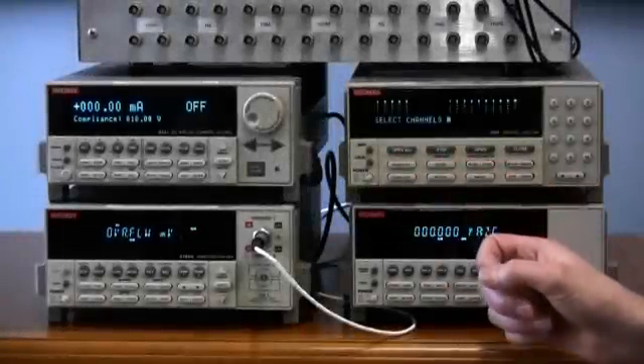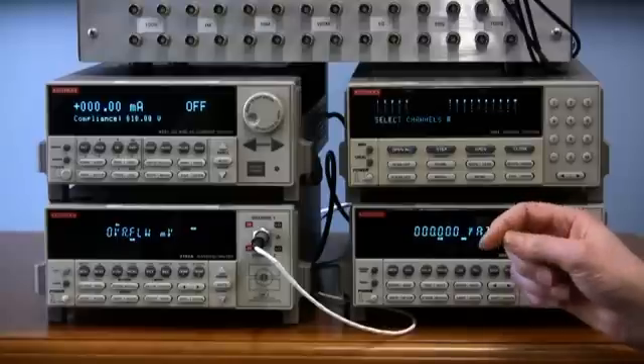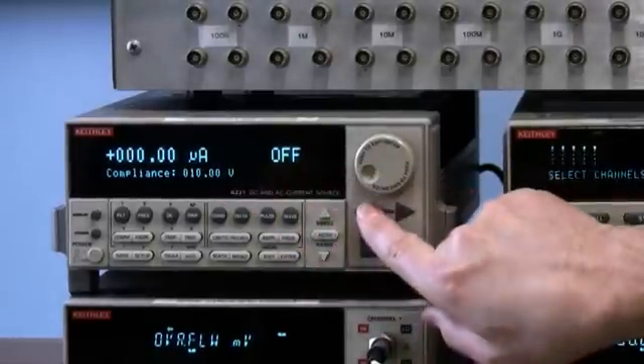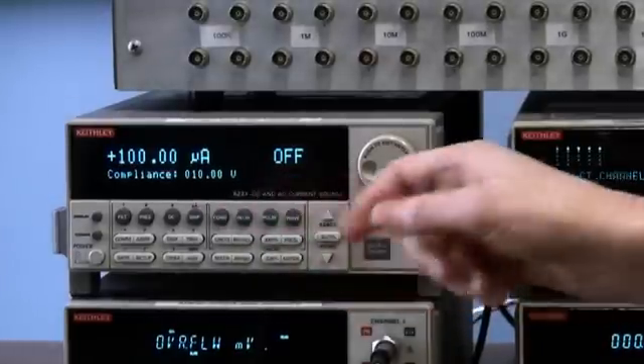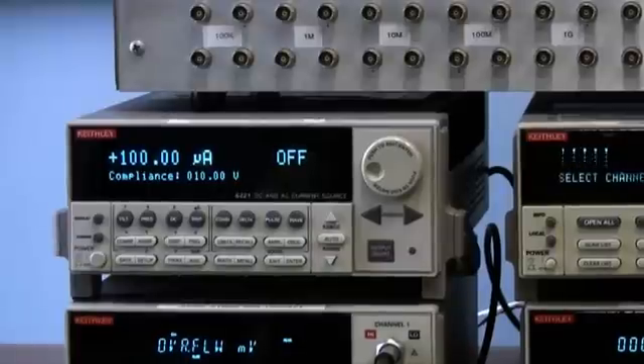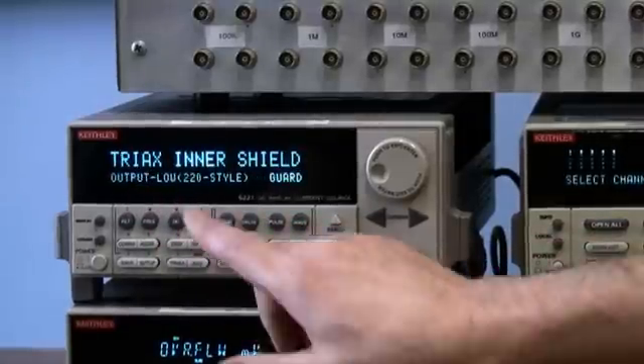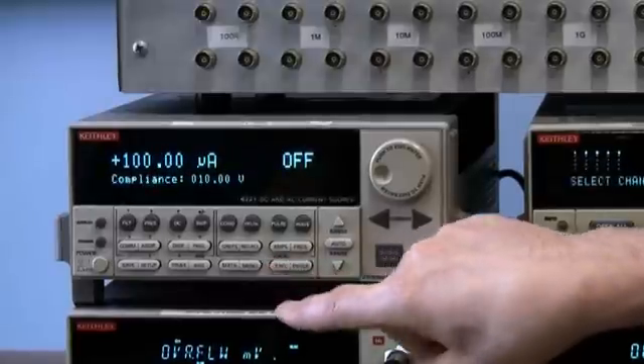Let's start with setting up the current source. Since we're going across a sample that is a 10k ohm square, which is really about 7.5k ohms, we're only going to source 100 microamps. We go down range until it's set to the 100 microamp range, then input 100 microamps and press Enter. Now it's set for 100 microamps. We also need to set the output low, or inner shield of the triax connector on the current source, to guard. We press the triax button, look for inner shield — it's blinking — select guard, press Enter, and it's all set. That's the setup of the current source.